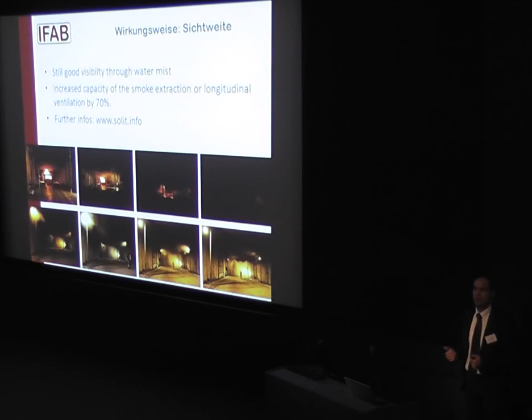Of course, you have at the beginning some kind of mixture of this strong smoke layer, but normally it's not to the ground level. It's just a mixture. And now what you see is there is no smoke anymore. There is no backlayering anymore. There's no change in the heat release rate. There's no change in the smoke extraction system. This is a picture showing an even worse effect when we had a very strong backlayering. We turned on the water mist system, and the smoke really disappeared within a short period of time.